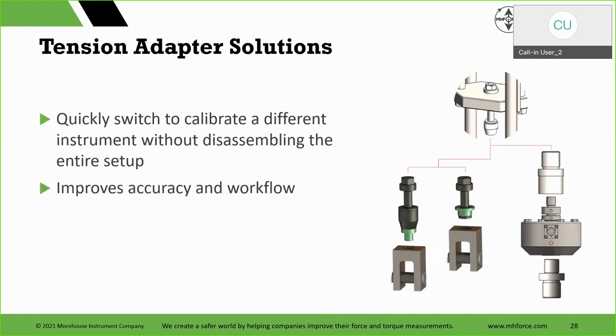Advantages of cal machine tension adapters: quickly switch to calibrate different instruments without disassembling the entire setup. If you have multiple tension links that come in, if you have a tension link and a load cell, it improves accuracy and workflow. I'm a big fan of lean. I've been a fan of lean for a while, not eating lean. I'm also a fan of that, but those that know me know I don't always do that. But really a fan of lean setup, which means, you know, what are my times? How long does it take a technician to set things up? It's that setup cost, right?